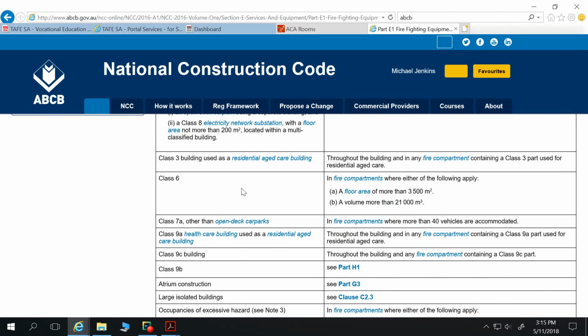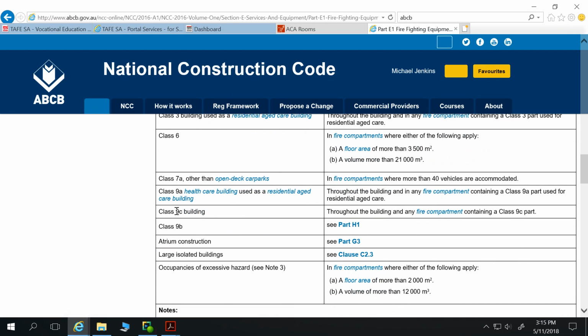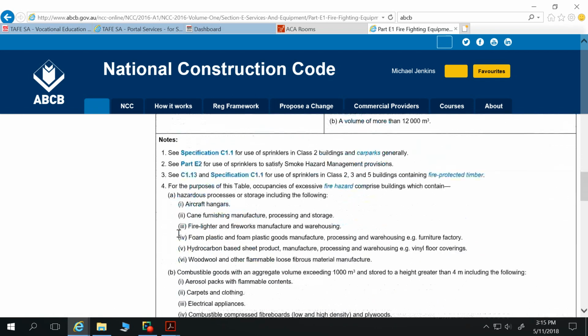Won't put words in your mouth, but if we were a Class 6 building in fire compartments where either of the following apply: a floor area of more than 3,500 square metres. Are we going to be that much, do you think? 3,500 square metres? No, I think we do need it. No. Or a volume of more than 21,000 cubic metres? No. Don't think we're going to be meeting that. Class 7, we're not one of those. Class 9, we're not one of those. Class 9C, 9B, not one of those. So, cool. We don't need to have sprinkler systems.